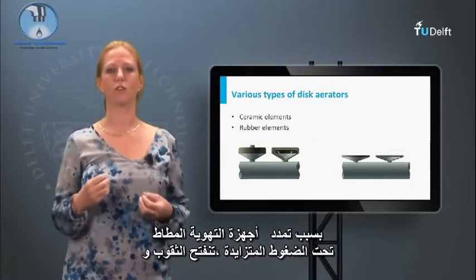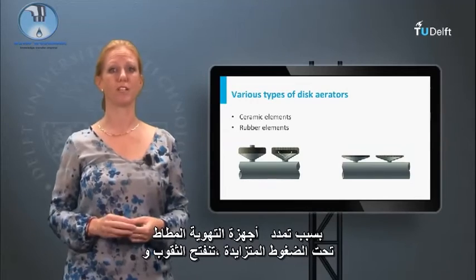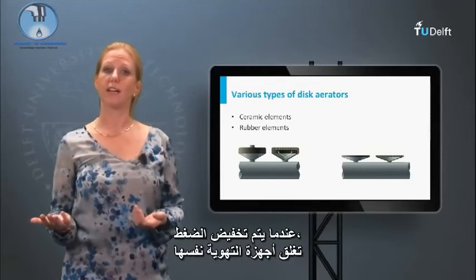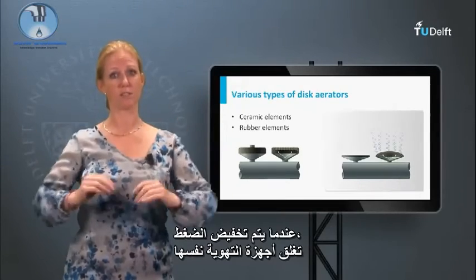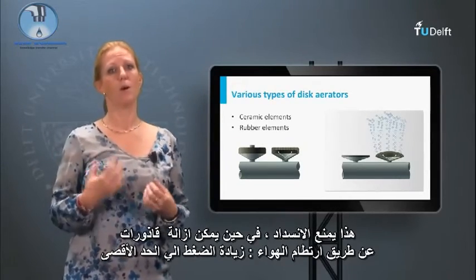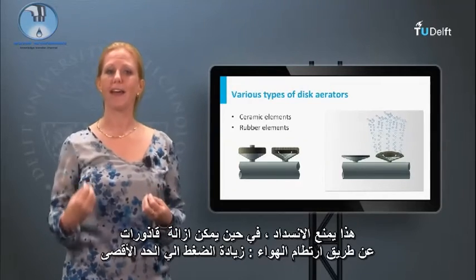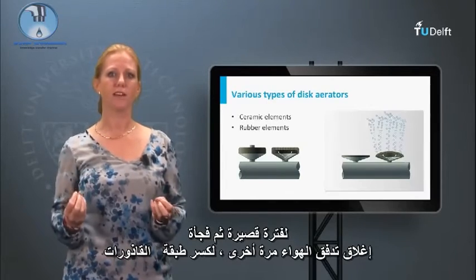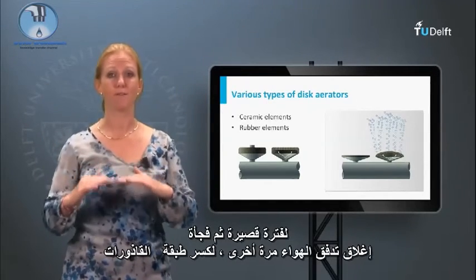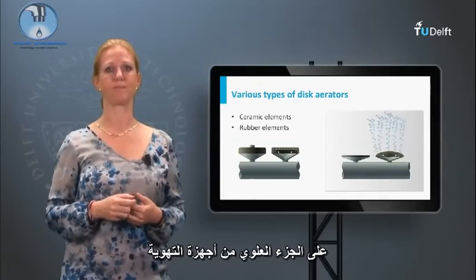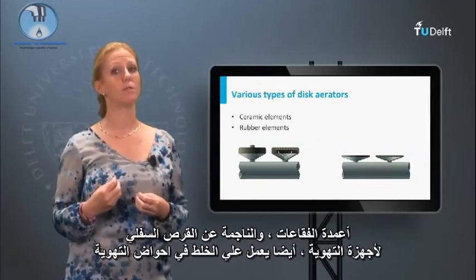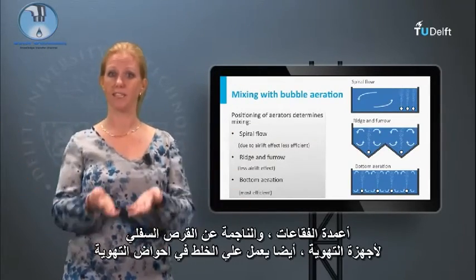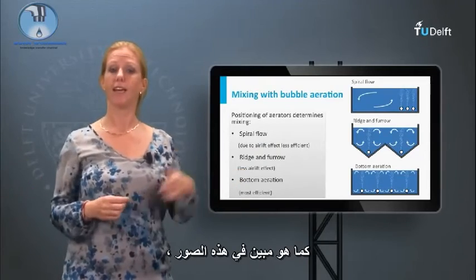Due to the expansion of rubber aerators under increased pressure, the holes open and air can escape. When the pressure is released, the aerators close themselves — this prevents clogging, while fouling can be removed by air bumping: increase to maximum pressure for a short while and then suddenly close the air flow again to break the fouling layer on top of the aerators. Bubble columns caused by the bottom disc aerators also introduce mixing in the aeration tanks, as shown in these pictures.